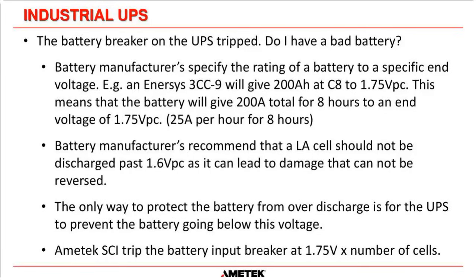So the only way to protect the battery from over discharge is for the UPS to prevent the battery going below this voltage. So an AMETEK SCI UPS will trip the battery input breaker and transfer the system to bypass when the system gets down to 1.75 volts times the number of cells. So if you walk up to a system, especially if you've had a power outage recently in your plant and you find that the battery breaker is in the tripped position, it's probably because the batteries have reached their end voltage, and all you need to do is reset the breaker and the charger will charge the batteries back up again.